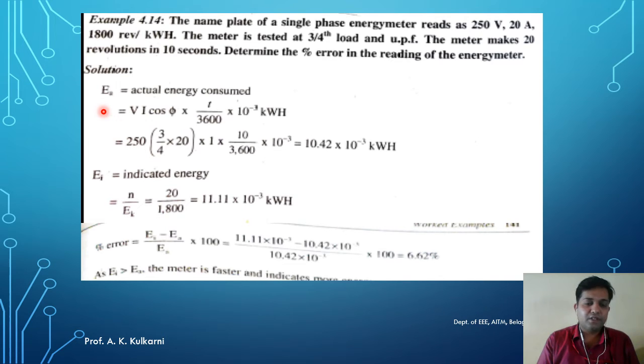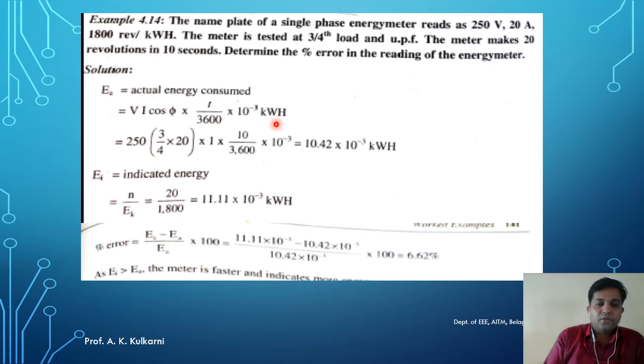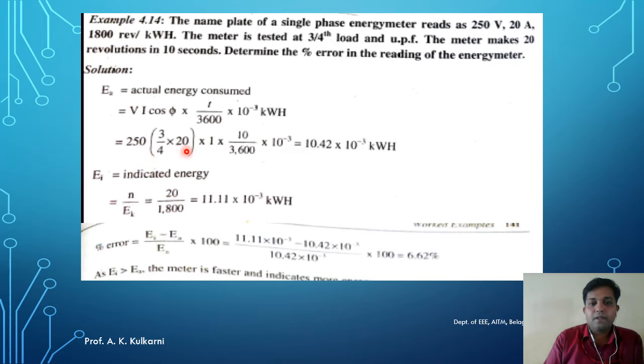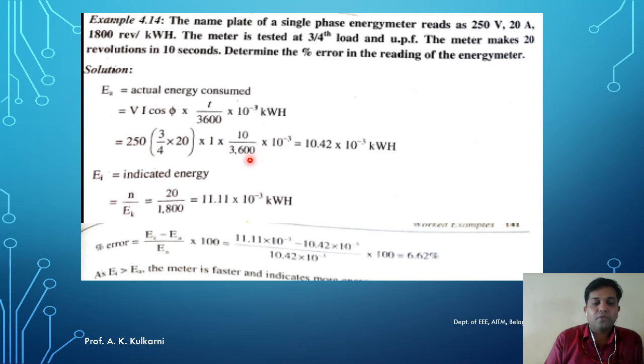First, let us find the actual energy consumed by the energy meter, which is V × I × cos φ × T divided by 3600 × 10⁻³ kilowatt hours. The applied voltage is 250 volts and the current is 20 ampere, but the meter is tested at three-fourth load, so the current becomes (3/4) × 20. The power factor is unity, so cos φ = 1. The time is 10 seconds, so T = 10/3600.